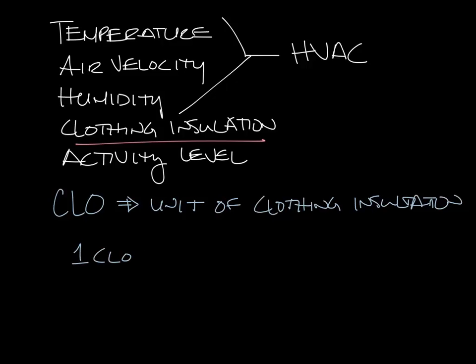So specifically, 1 CLO equals 0.88 square feet Fahrenheit over BTUH, and since BTUH is BTU per hour, we'll move the hour up here. So that's 1 CLO, and that is also equal to 0.88 R.